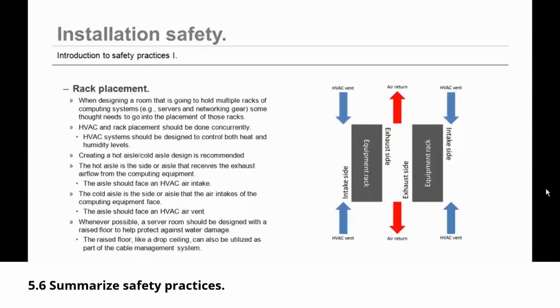Let's talk about rack placement. When designing a room that is going to hold multiple racks of computing systems, some thought needs to go into the placement of those racks. HVAC and rack placement should be done concurrently. Heating, ventilation, and air conditioning systems should be designed to control both heat and humidity levels. When multiple racks are going to be installed, creating a hot aisle, cold aisle design is recommended. The hot aisle is the side of the aisle that receives the exhaust airflow from the computing equipment. This aisle should face an HVAC air intake. The cold aisle is the side or aisle that the air intakes of the computing equipment face. This aisle should face an HVAC air vent.